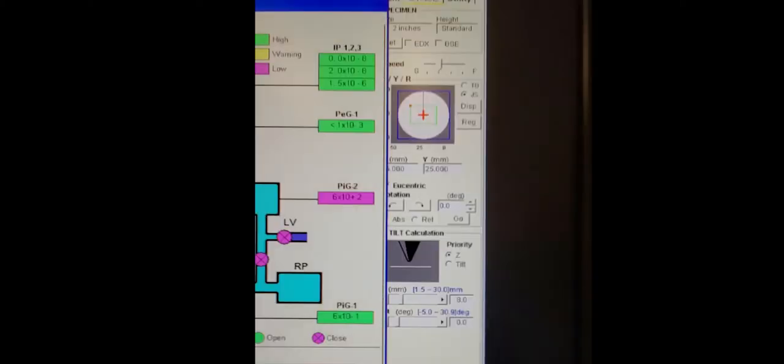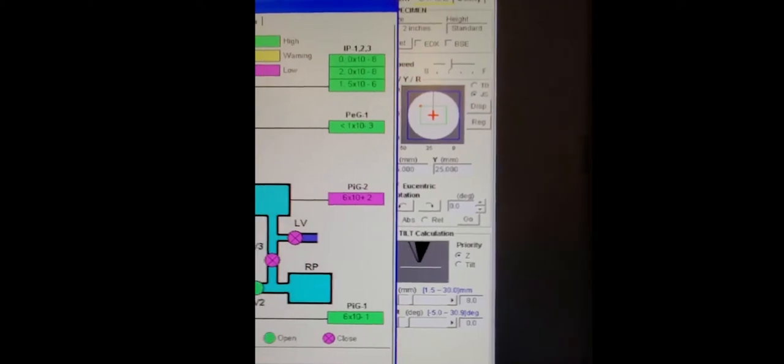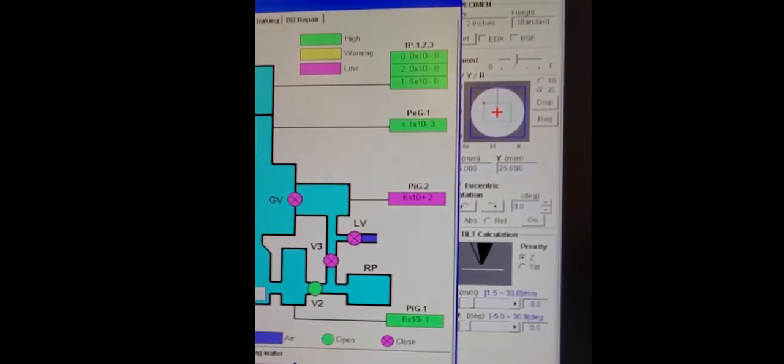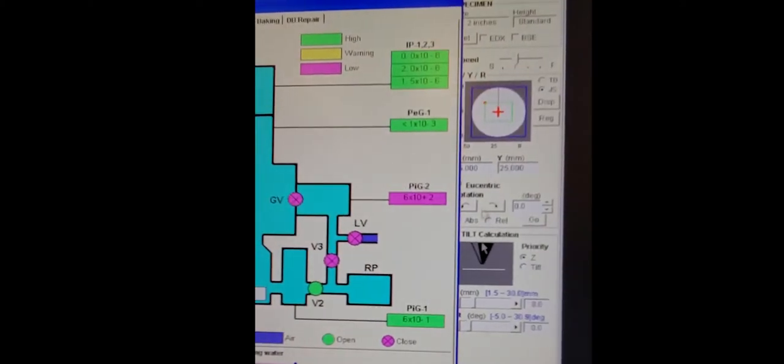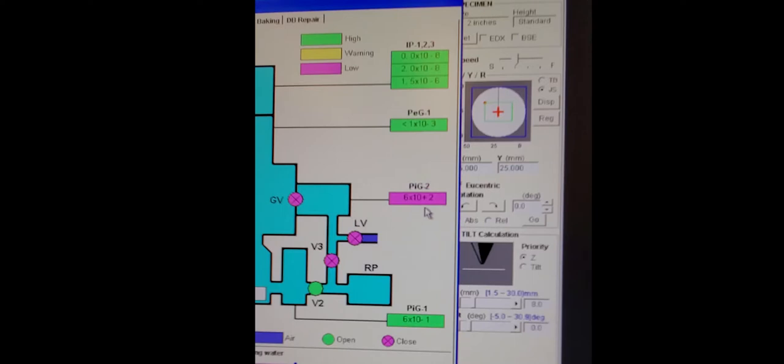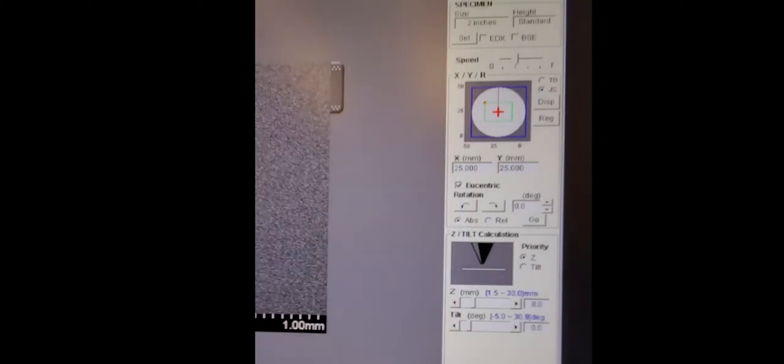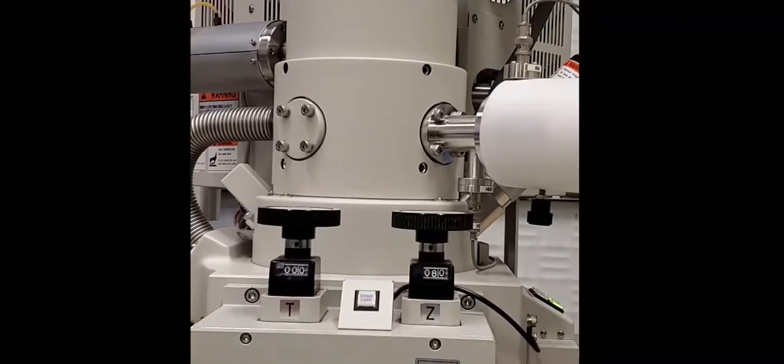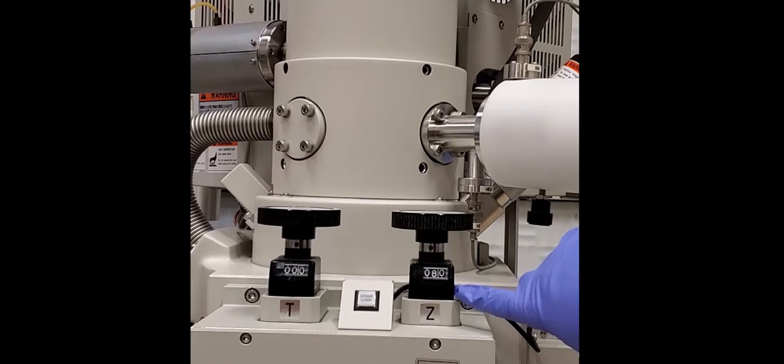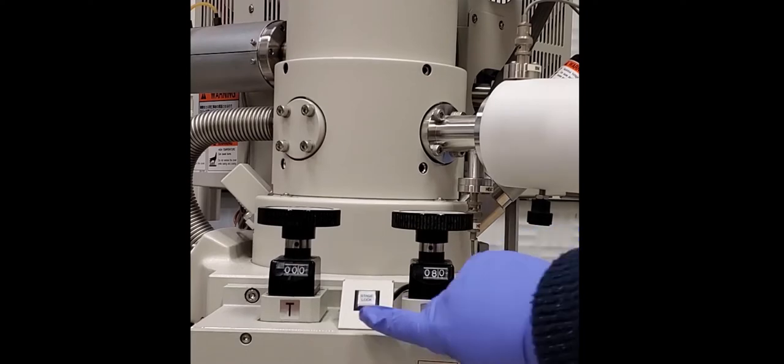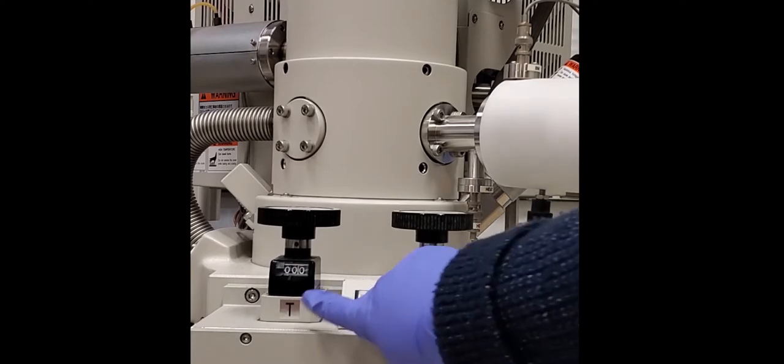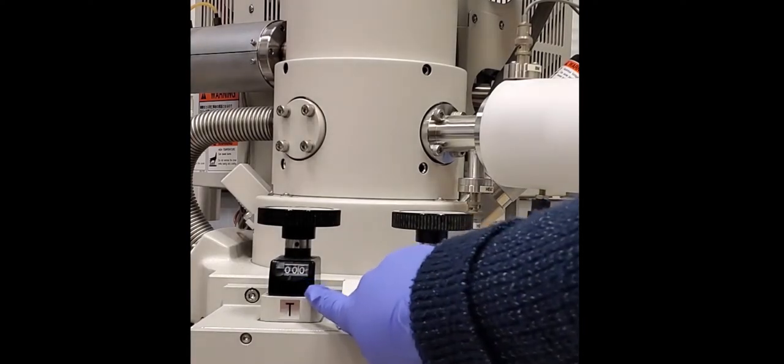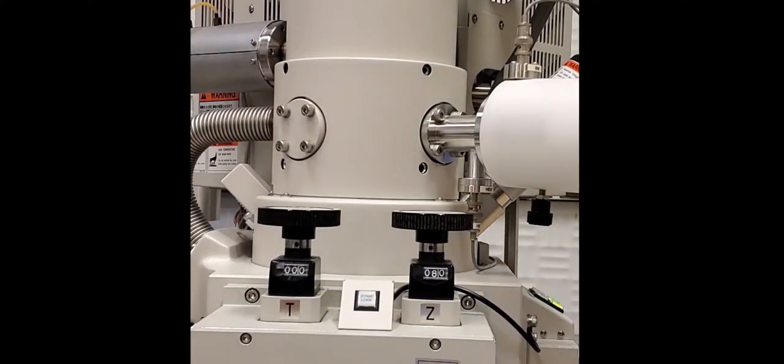Next, we'll move down here to the bottom right. We're going to click the maintenance button. It's going to open a window and you can see the top three and then the one below that. These boxes should all be green. If they're not, you should contact staff before you decide to use the instrument. This box is pink, but it's okay to still use the instrument. In the front of the instrument, also check that the Z height is at eight millimeters, the stage is not locked, and the tilt is at zero.